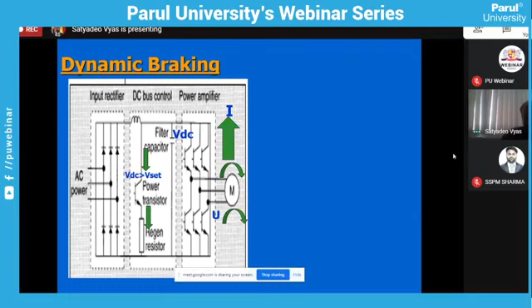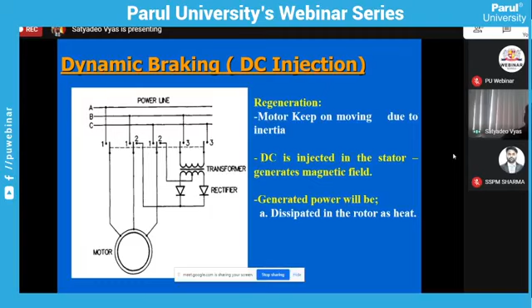One is the DC injection method. DC injection, what happens? When there is stored energy in the motor, after switching off the motor is rotating, but we need to stop it immediately. Then we can inject the DC supply in the stator of the motor. What will happen? That DC supply will generate flux in the air gap. As the rotor is rotating and magnetic flux is generated by DC, then what will happen? The flux gets linked to the rotor and the energy will be dissipated in the rotor circuit.